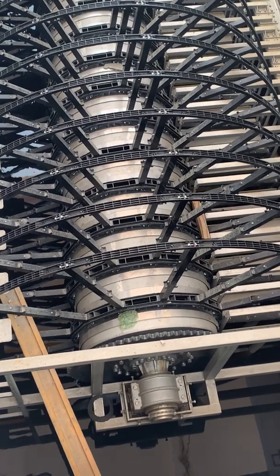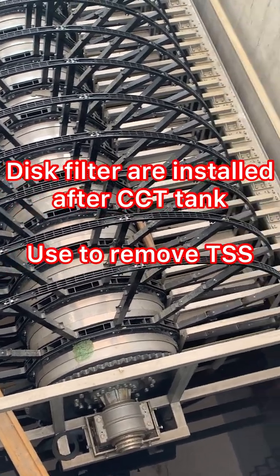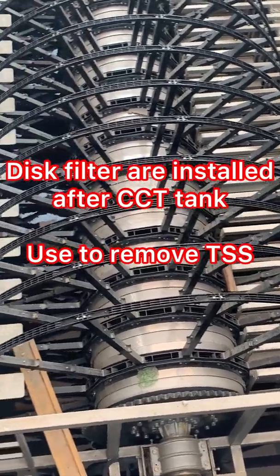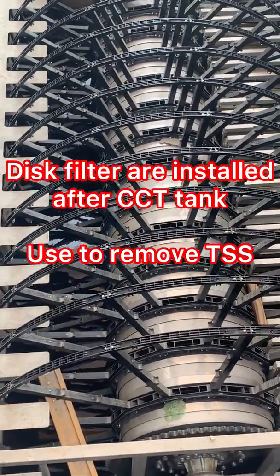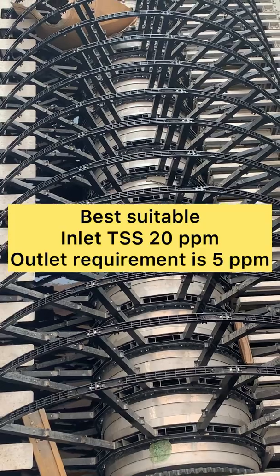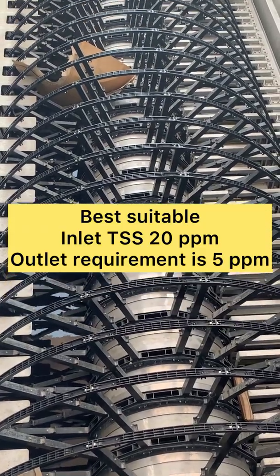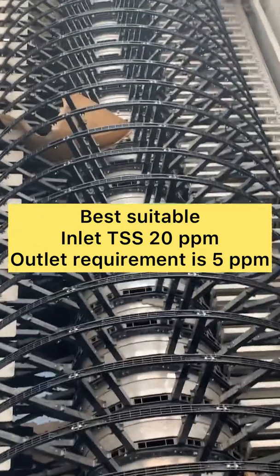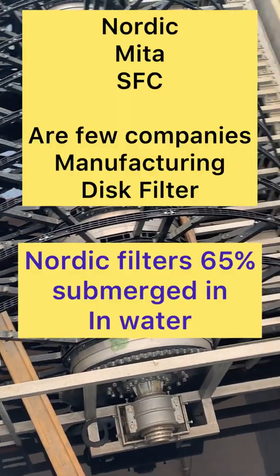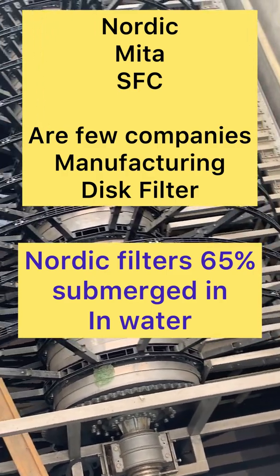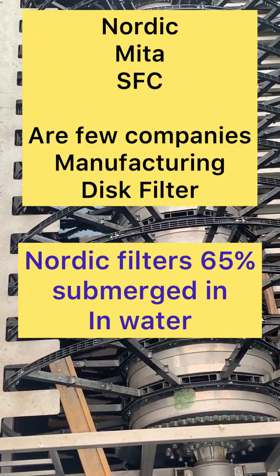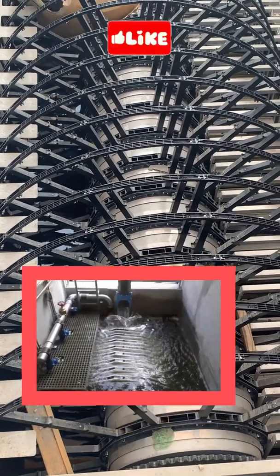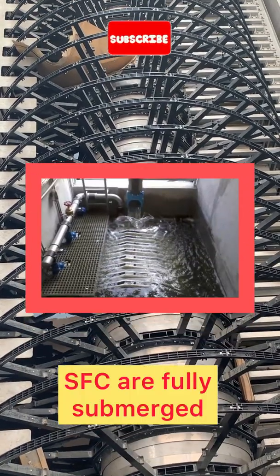This filter is used for removal of suspended solids, where the inlet TSS is 20 ppm and outlet requirement is 5 to 10 ppm without chemical addition. These disc filters are 65% maximum submerged in water with the rest above it, whereas SFC filters are totally submerged in water.